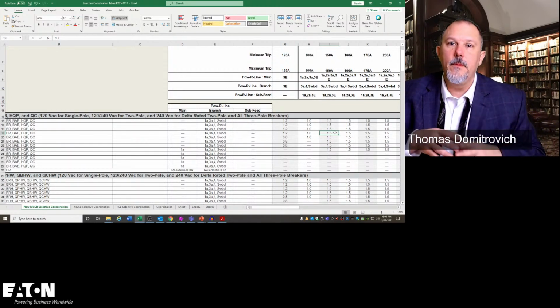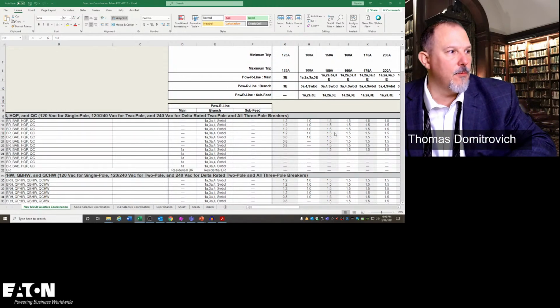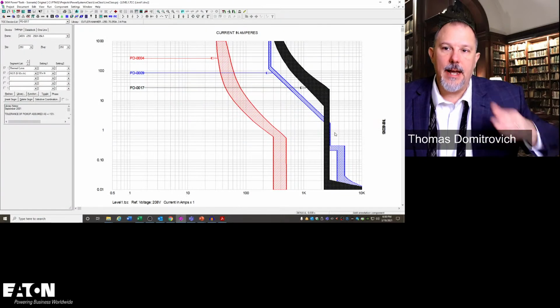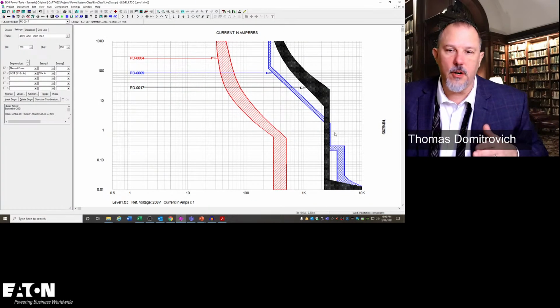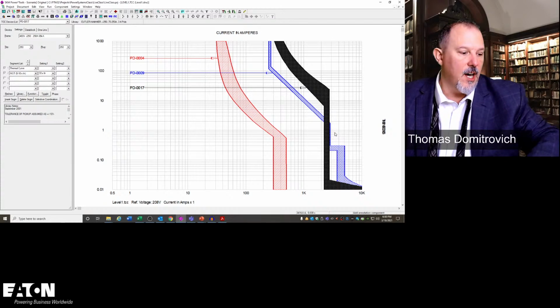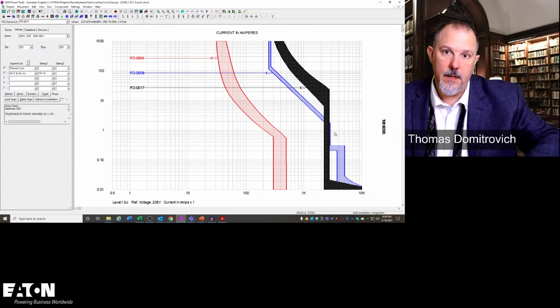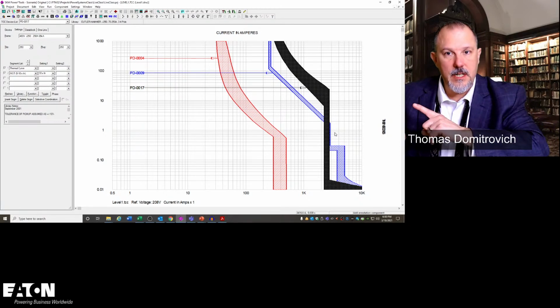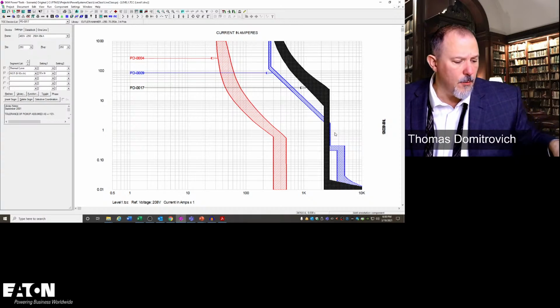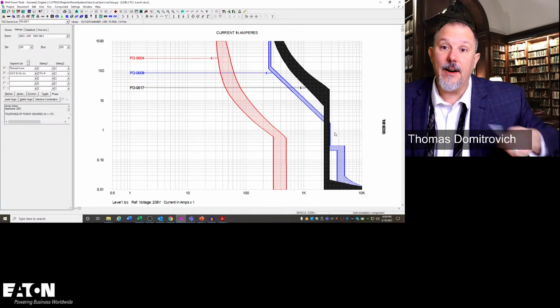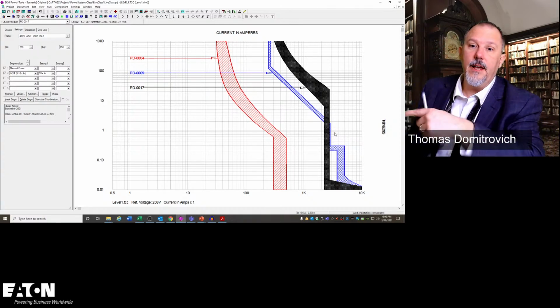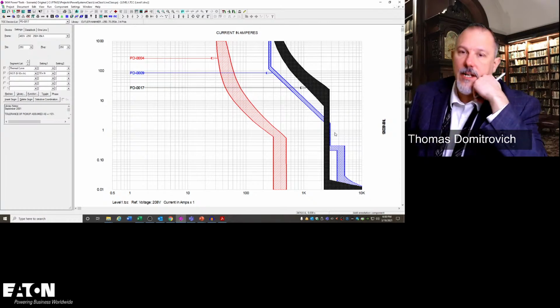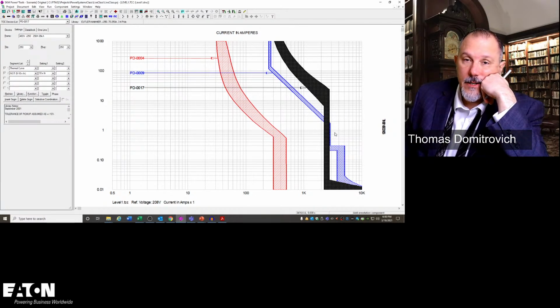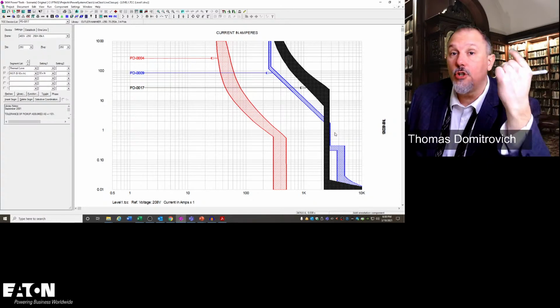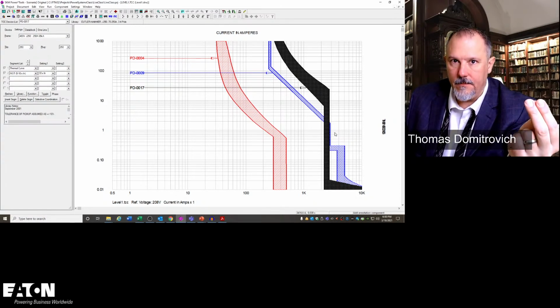When I am looking at my trip curve, and I have a fault current that's higher than the instantaneous pickup of both of my devices, based upon the TCC curve, I would say they don't selectively coordinate. Now, I know a lot of engineers that'll look at these curves and say they selectively coordinate because I have separation all the way down to 0.01 seconds. Selective coordination is not about time. Selective coordination is about current and time.